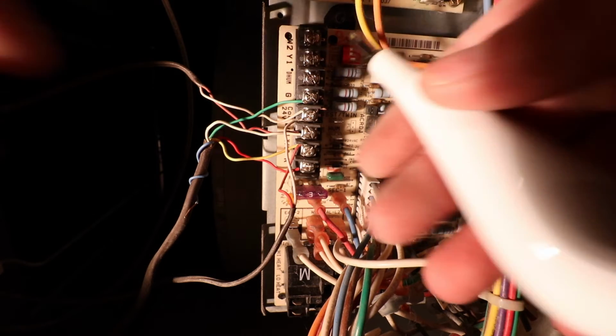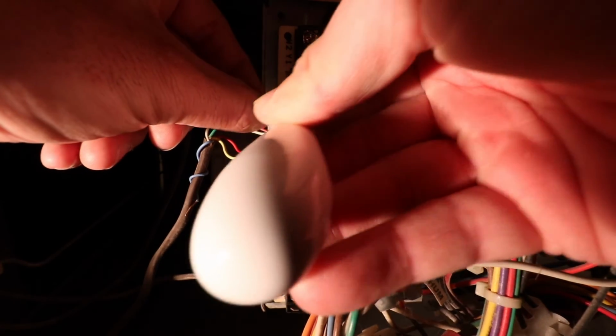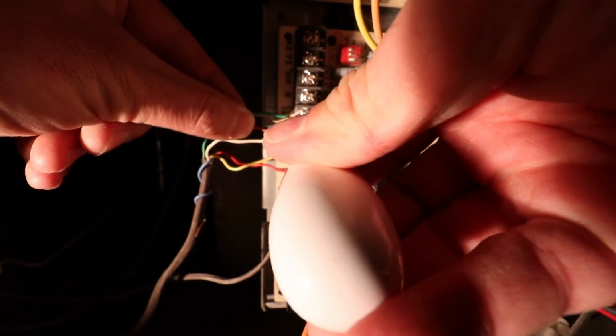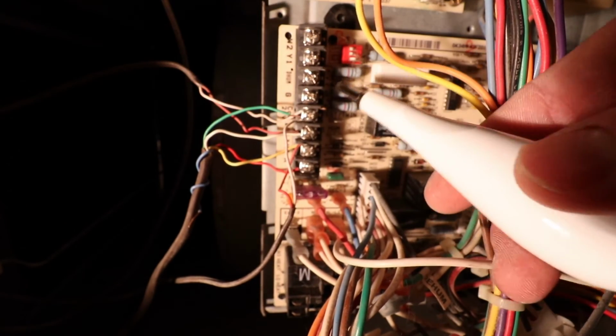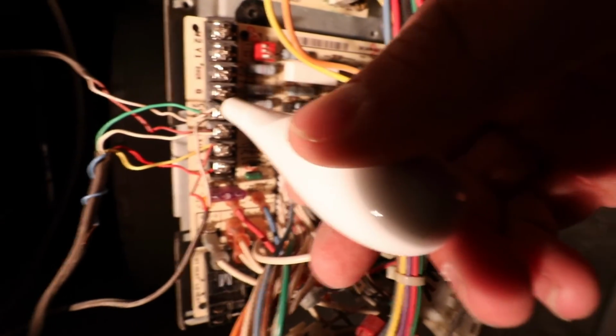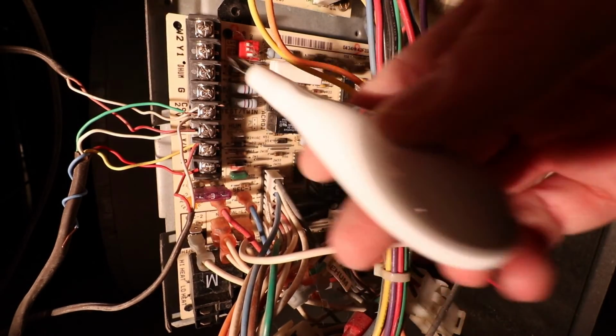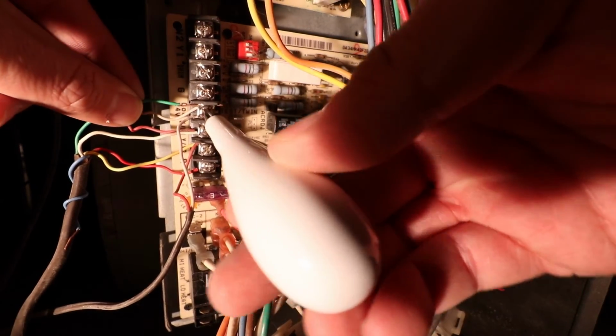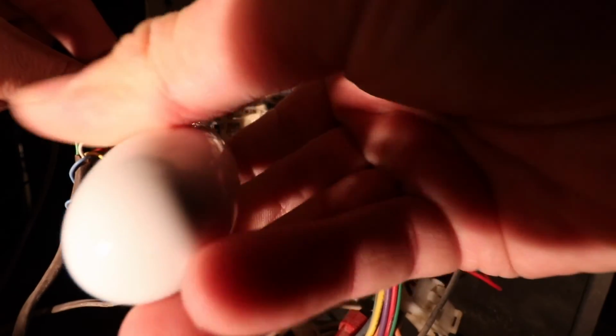But if you don't have the common wire, all you're going to do is take your G wire, which is your fan wire right here, and move it down to the common wire terminal, which for us is the very next terminal. We'll loosen it a little bit so we can fit it in with the other wires in that terminal, and then tighten it down.